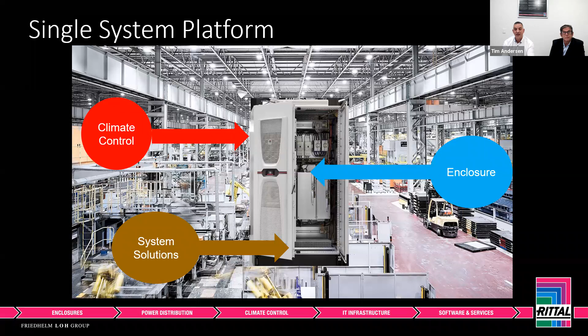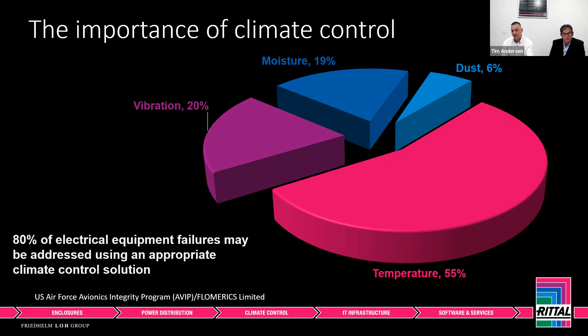So why is climate control such an important factor in enclosure designs? Research of electrical equipment failures has identified that while vibration accounted for 20% of breakdowns, the remaining 80% was caused by temperature, moisture and dust. These three factors, adding up to that 80%, can be addressed and minimized by using the appropriate climate control products and/or solutions.